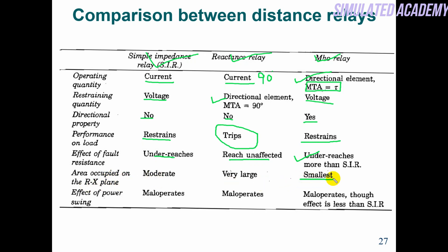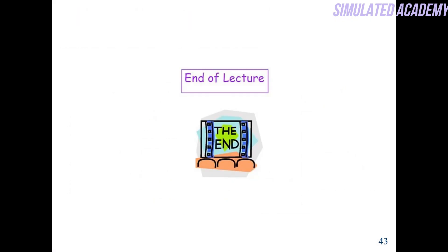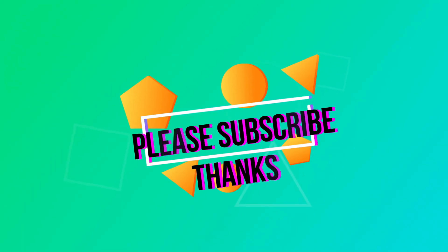Area occupied: the Mho relay occupies the smallest area, the simple impedance relay has a large area since it is a circle, and the reactance relay — being a straight line — covers the most area below it. Effect of power swings: the simple impedance relay is most affected by power swings, the Mho relay and reactance relay also operate on power swings, but the Mho relay is affected least. So that is how you protect your transmission line using different relays. If you haven't subscribed to my channel, please kindly subscribe. Thank you so much.